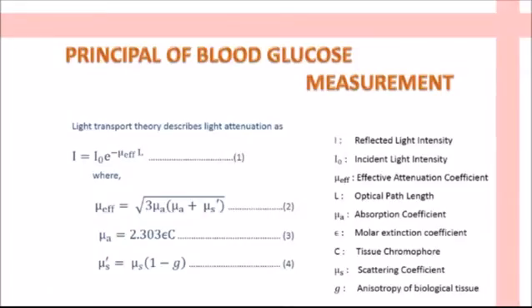Now we will see the actual principle of blood glucose measurement. According to light transport theory, I equals I-naught into e raised to minus mu-effective into L, where I is the reflected light intensity, I-naught is the incident light intensity, mu-effective is the effective attenuation coefficient, and L is the path length. The effective attenuation coefficient depends on the absorption coefficient as well as the scattering coefficient of the cell.